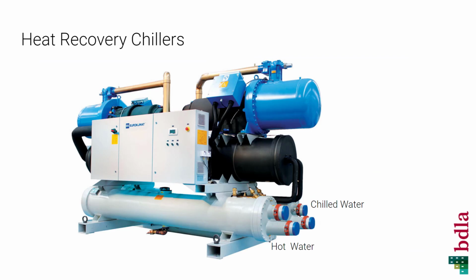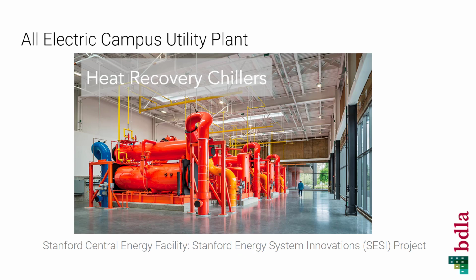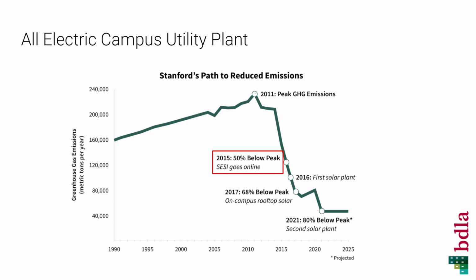Heat recovery chillers are capable of creating hot water and chilled water, and can have some great efficiency benefits in situations where both hot water and chilled water are often required simultaneously. One of the best applications for these is utility plants. The Stanford Central Energy Facility is a great example of how these can be applied. They have a whole bank of heat recovery chillers, making chilled and hot water for the entire university campus. Because there's such an array of different buildings and different uses, they need hot water and chilled water both at almost all times. This really has efficiency benefits, and you can see that when Stanford transitioned to this new plant, their peak energy and emissions reduced by 50%. And with the addition of renewable energy, they're very close to an entirely carbon-free campus.